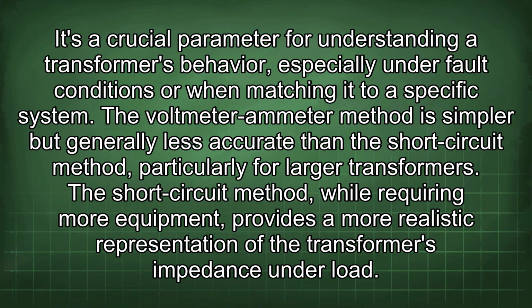It's a crucial parameter for understanding a transformer's behavior, especially under fault conditions or when matching it to a specific system. The voltmeter-ammeter method is simpler but generally less accurate than the short-circuit method, particularly for larger transformers. The short-circuit method, while requiring more equipment, provides a more realistic representation of the transformer's impedance under load.